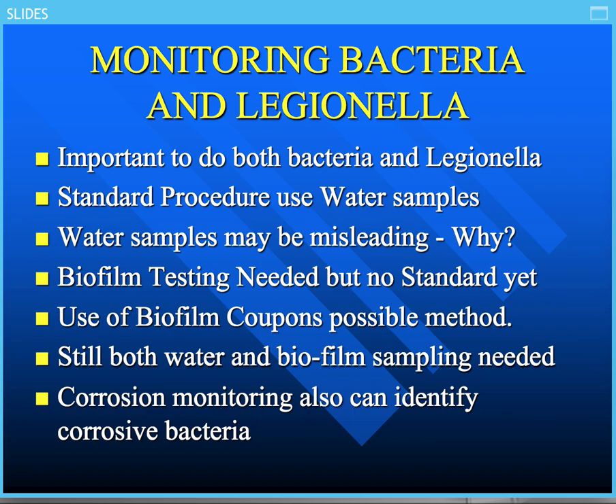What do you mean by misleading? Well, if you're taking a water sample and it says I have a very low level of total bacteria, even a low level of Legionella, the big question is, wait a minute, what if I have biofilm in my system? Biofilm is the biological film created by the microbiological organisms, and that's where many of these organisms like to live, the corrosive ones particularly. In the past, we've monitored corrosive bacteria by taking samples of the biomass, but not for total bacteria or for Legionella. We should actually be taking a biomass sample and determining what that biomass is.